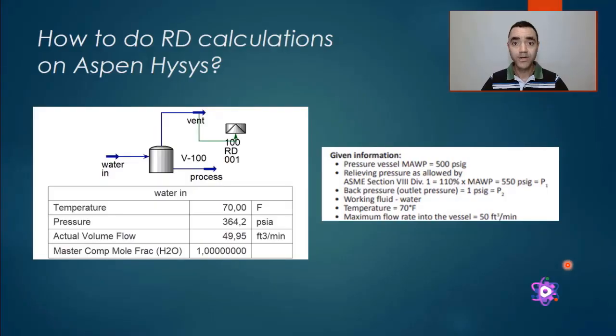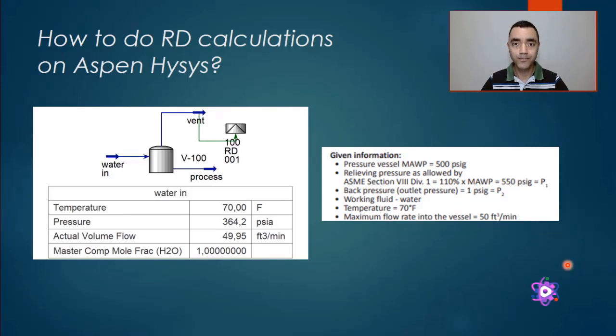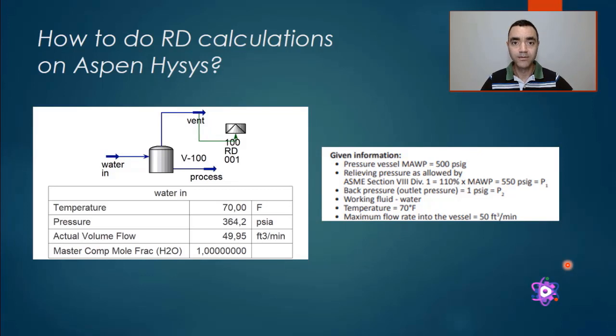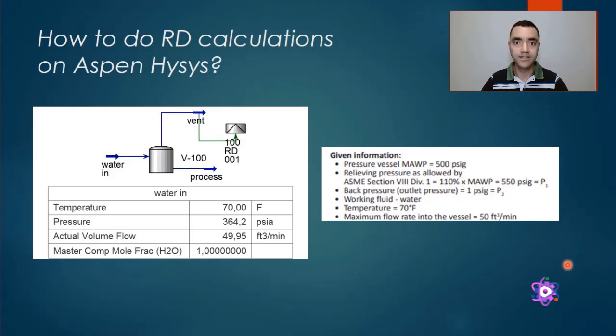It's important to mention that ASPEN HYSYS, at least on v11, performs only the coefficient of discharge method calculations. So you need to comply with the requirements of the arrangement, venting to atmosphere, etc., that you can find in the standards.